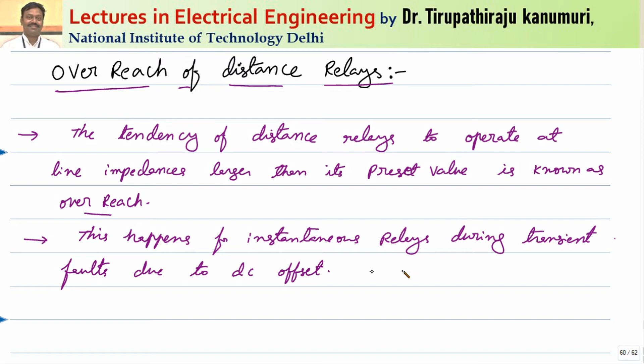Hi all, today we are going to discuss overreach of distance relays. The tendency of the distance relays to operate at line impedances larger than their preset value is called overreach of the relay. This mainly happens for instantaneous relays only, which operate instantaneously during the transient faults. That happens because during the transient faults there will be a DC offset value.